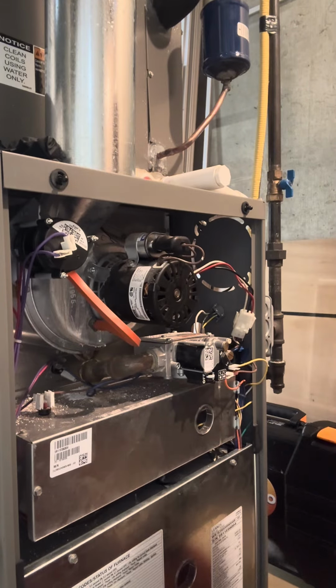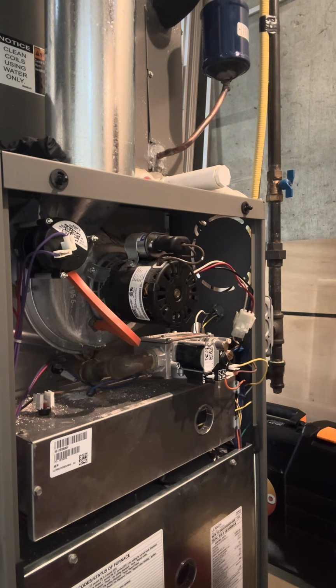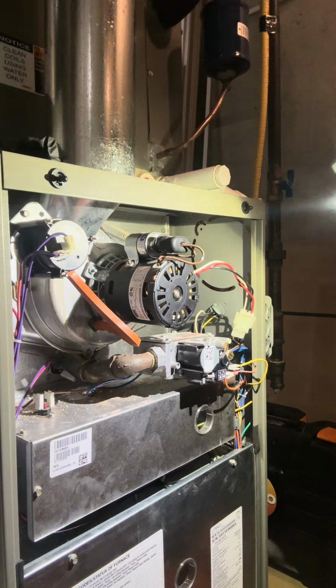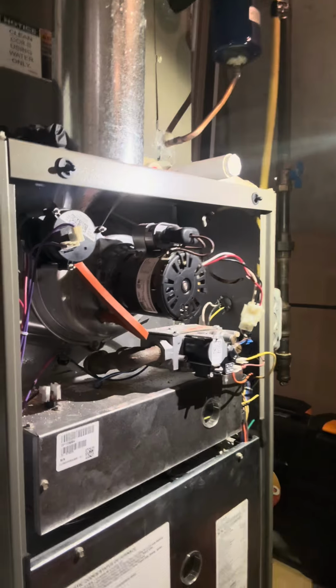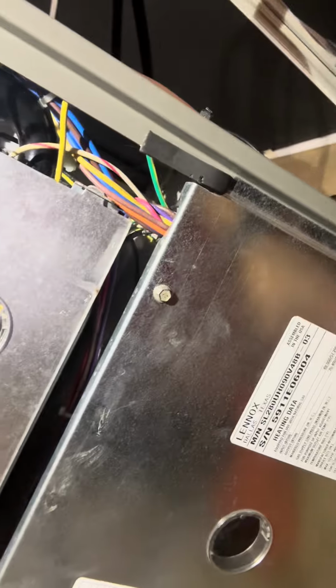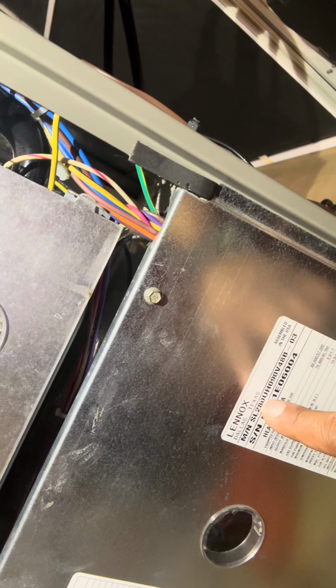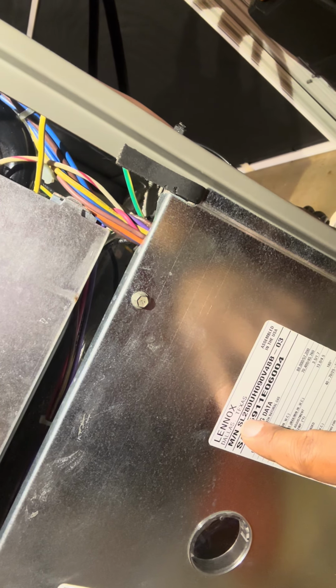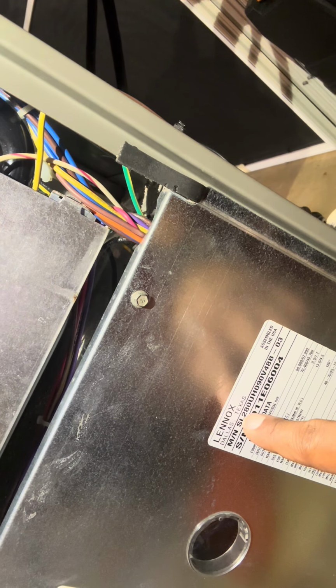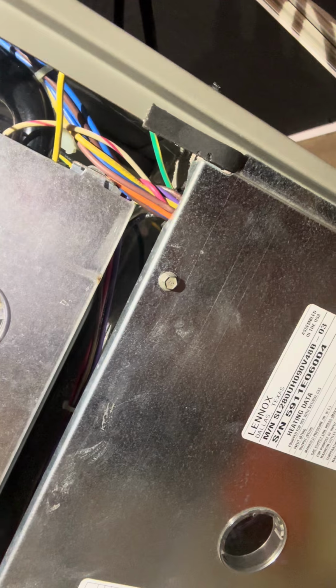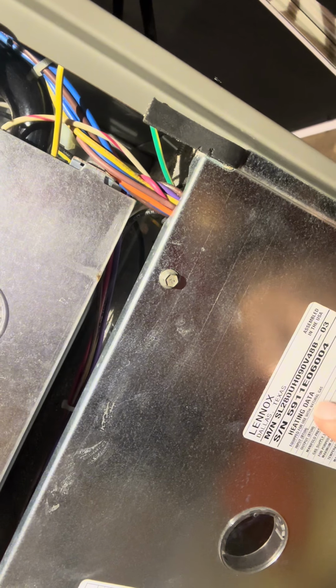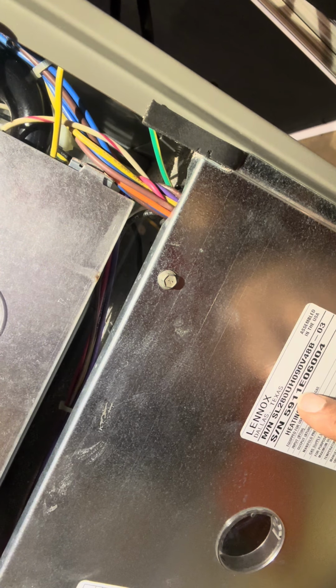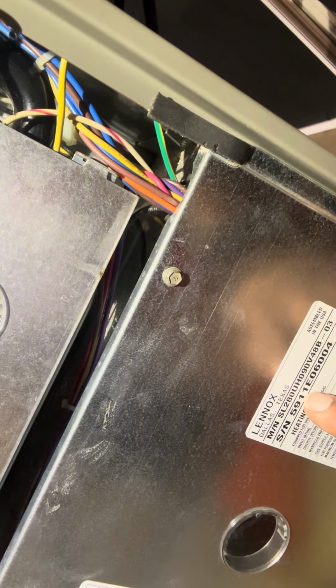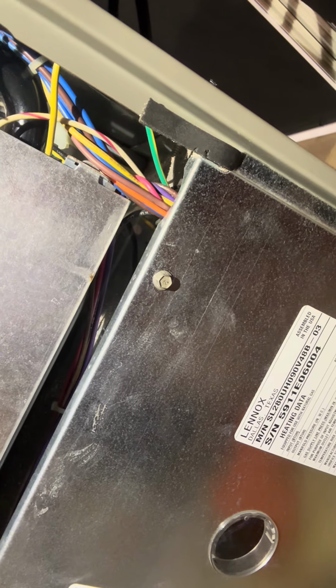So just a little bit of background on this furnace. This is a 2011 SL280. If you want to take a look at this data tag, you can see SL280. SL is the signature line. 2 is a 2-stage furnace, and it's an 80%er. So that's really how you tell. With Lennox, you could tell the age of the system by the second set of numbers, which is this 11 here. So this is a 2011 model.